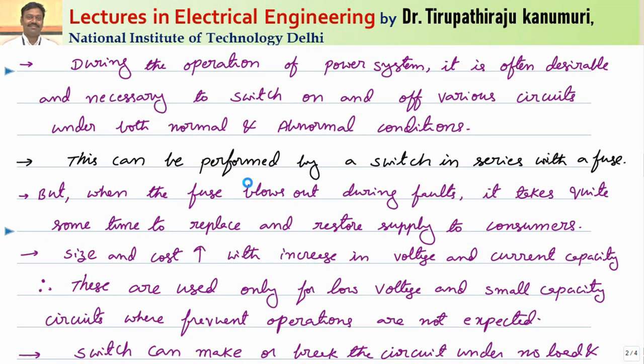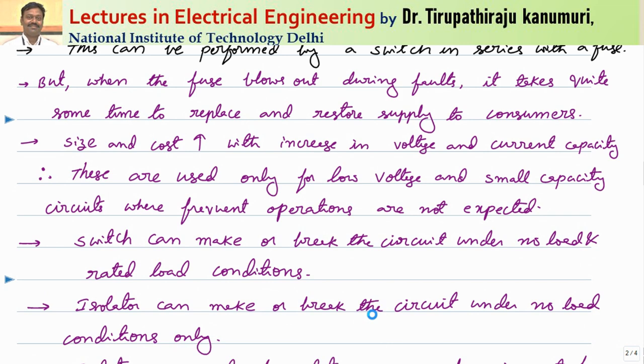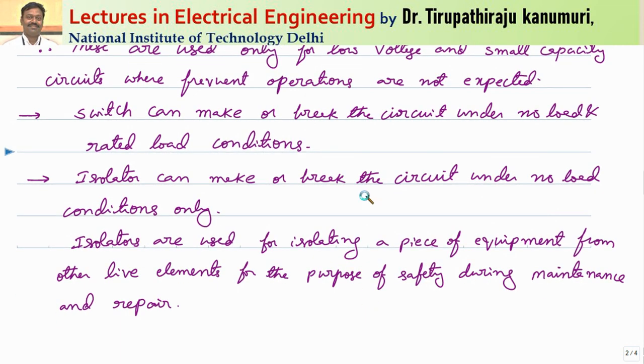During the operation of power systems, it is often desirable and necessary to switch on and off various circuits under both normal and abnormal conditions. This can be performed by a switch in series with a fuse, but if the fuse blows out during a fault, it takes quite some time to replace and restore the supply, and the size and cost increase with voltage and current capacity. That is why these are used only for low voltage and small current circuits where frequent operations are not expected. A switch can make or break the circuit under no-load and rated load conditions only. An isolator can make or break the circuit under no-load conditions only, and isolators are used for isolating a piece of equipment from other live elements for the purpose of safety during maintenance and repair.